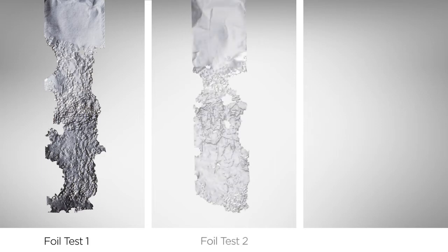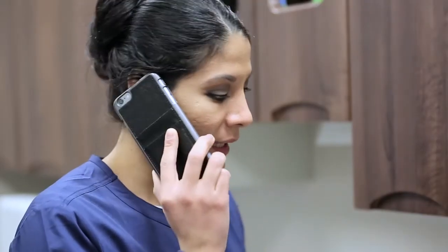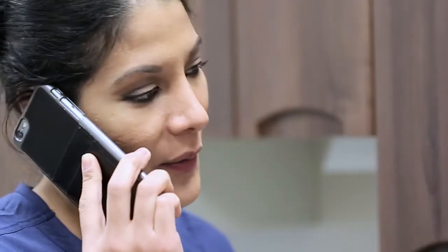It is critical to use this test to evaluate the results over time. If you see less pitting in subsequent tests, this could be an indication of reduced cleaning effectiveness. It is recommended that you perform this test a few times each year. If you are uncertain that your cleaner is producing similar results, consider contacting your dental dealer technical support team or retail representative.